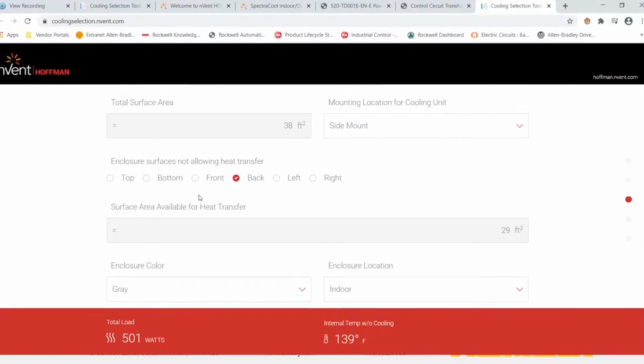When we get into definitions of what's allowing or not allowing heat transfer, typically it's about a 1-inch space between the enclosure and the wall. So if you're standing off there, there's probably some heat transfer being allowed. But if you're like me, you like to play it safe, so for a standard wall mount enclosure, I'll typically say the back is not allowing heat transfer, even if there's a little bit of space there.